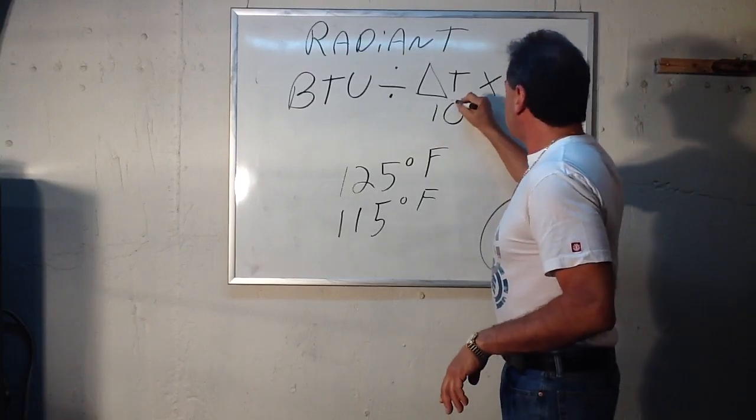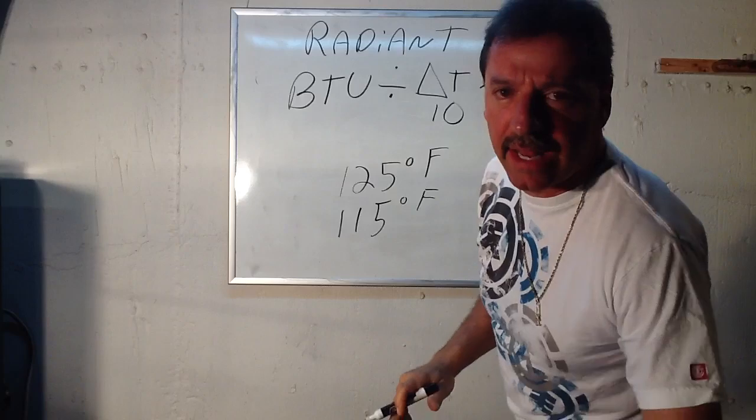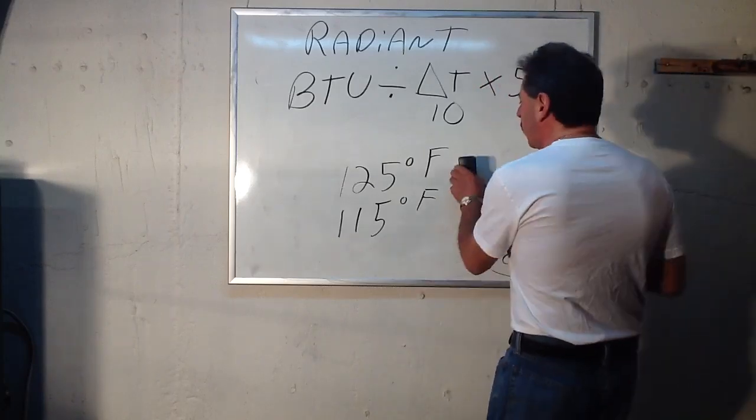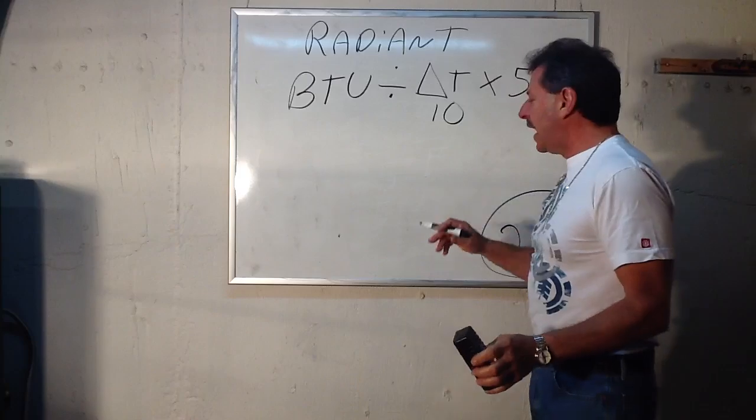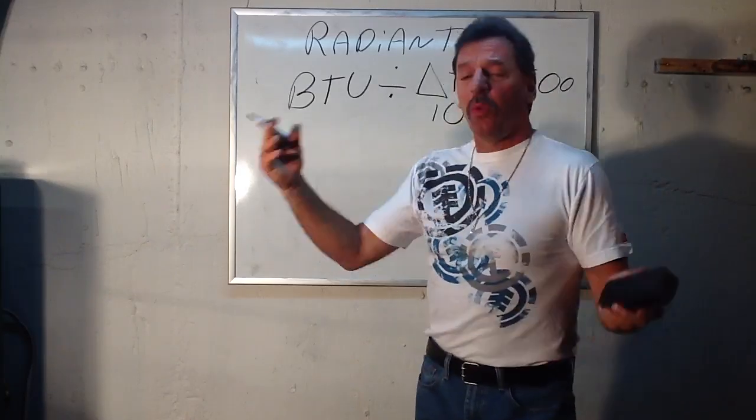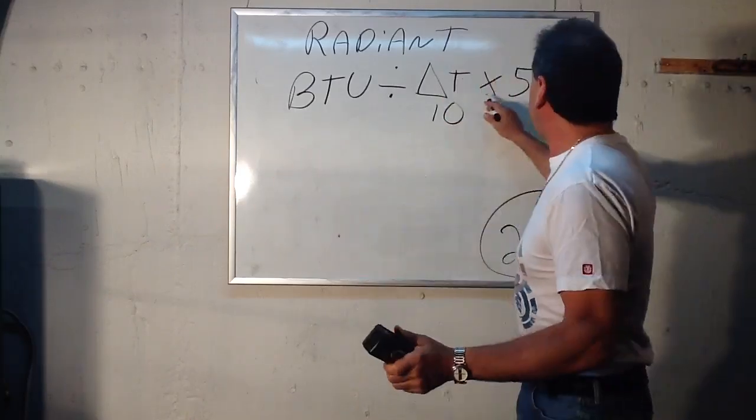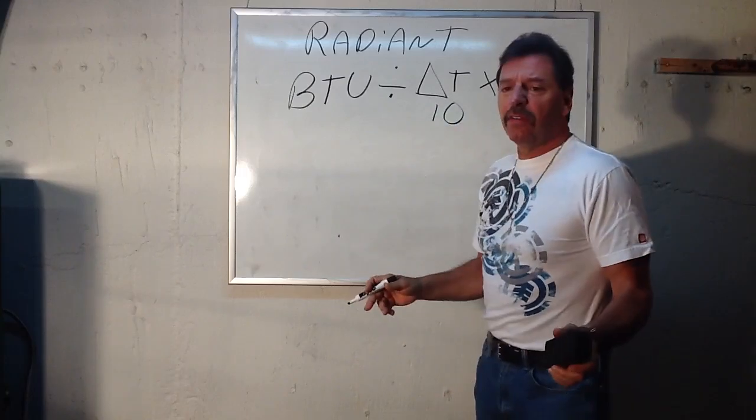I just want to get that crystal clear: with baseboard it's 20, with radiant heat it's about 10. Or if you raise your radiant heat, whatever the Delta T is, you use that number times 500 to get the flow rate.